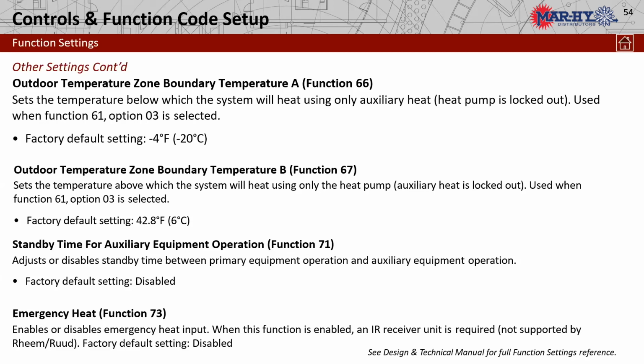Function 71, standby for auxiliary strips. So basically it's a time delay. If we are calling for strip heats, we'll set a time delay between the strip heat and its actual call. That can be from 2 minutes to 99 minutes. It's whatever you choose. I choose 5 minutes.